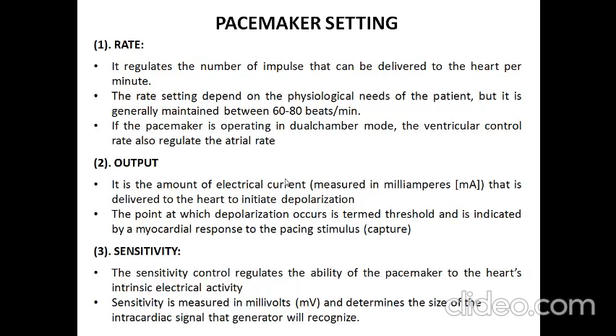the atrial rate. The second setting is the output. It is the amount of electrical current, normally in milliamps, which is delivered to the heart to initiate depolarization. The point at which depolarization occurs is named the threshold and is indicated by a myocardial response to the pacing stimulus. That is called capture. And the third important setting is sensitivity. The sensitivity control regulates the ability of the pacemaker to sense the heart's intrinsic electrical activity. Sensitivity is measured in millivolts and determines the size of the intracardiac signal that the generator recognizes.